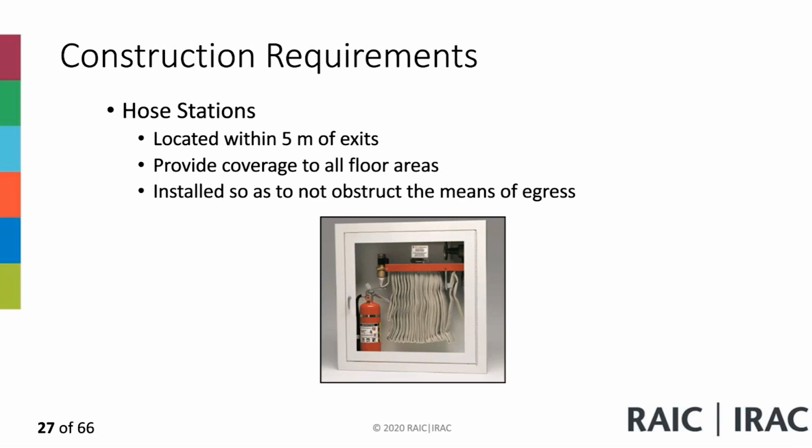But if you are designing a system, especially in industrial buildings or residential areas outside the cities, and you have to provide your own water supply, then you've got to take a look at the provision of 3.2.5.7, the appendix notes, to make sure you provide water supplies adequate enough for the building systems to work.